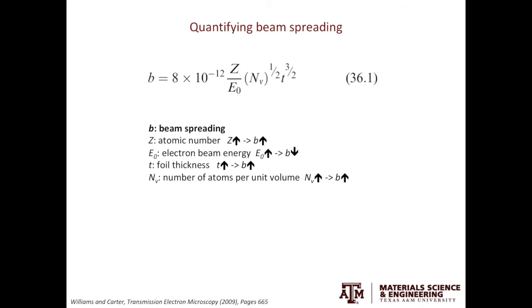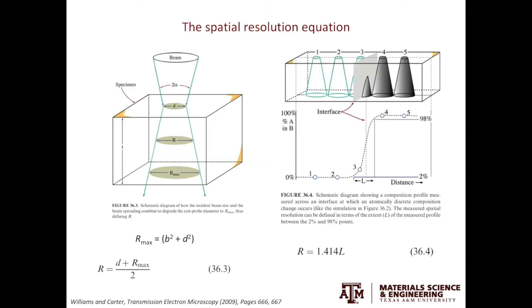As a TEM user, if you want to improve the spatial resolution of EDS in TEM, there are two things you can do. First, you can reduce the foil thickness. Second, you can use a TEM with higher acceleration voltage.